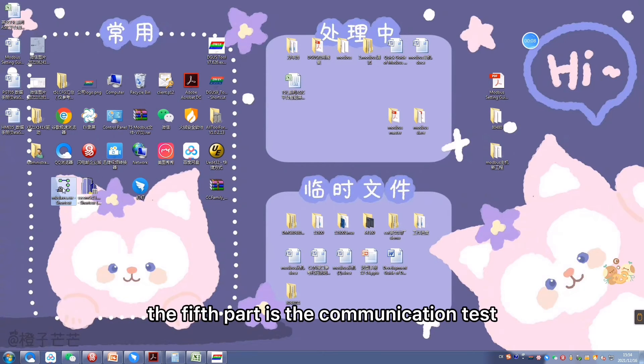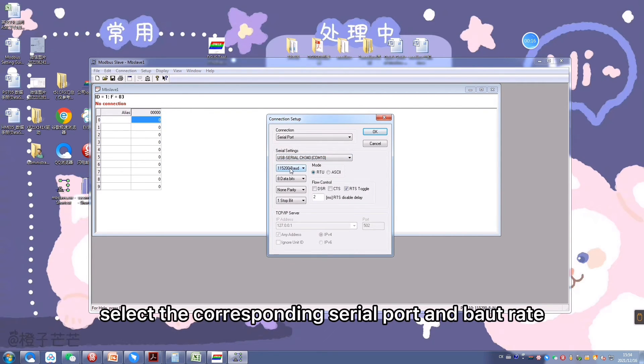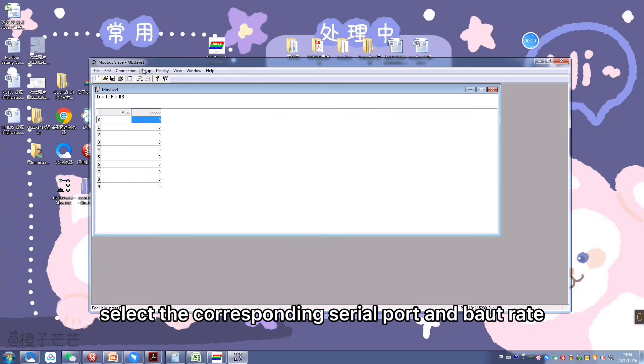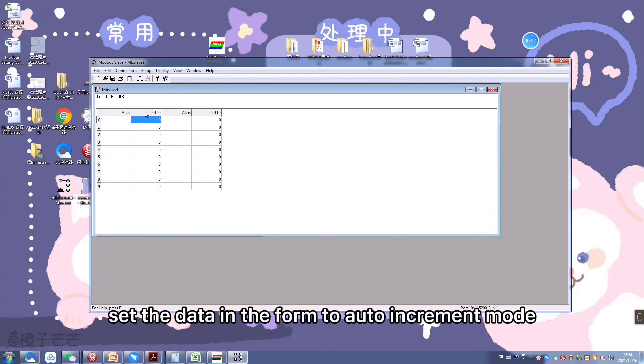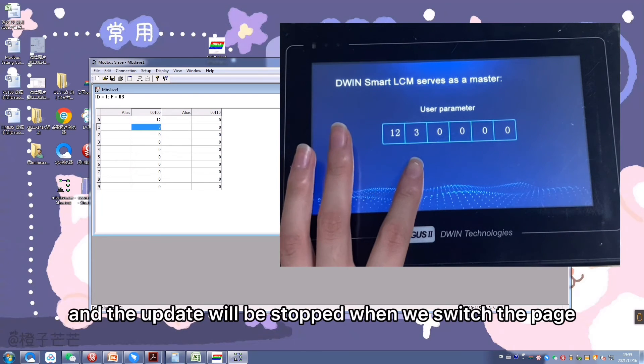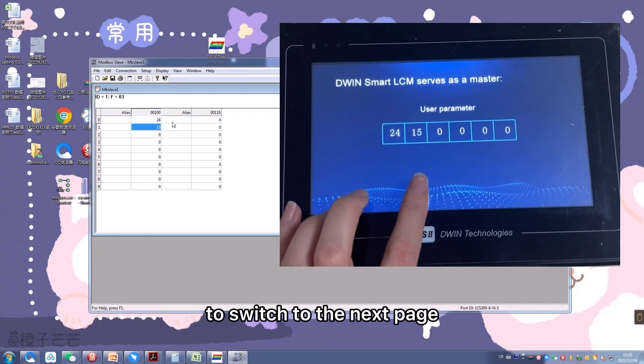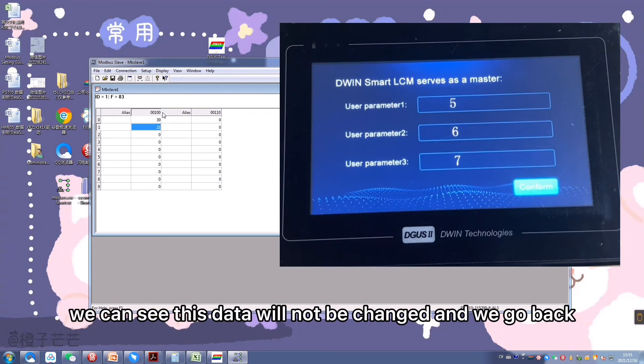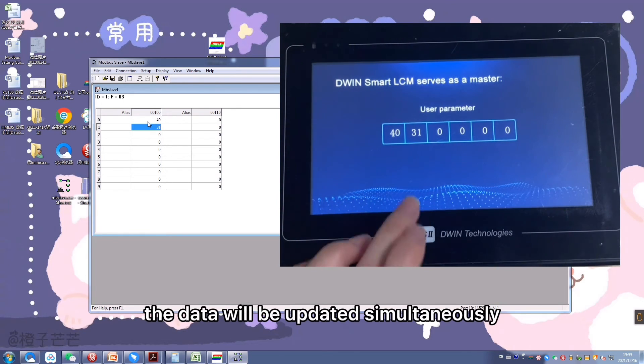The fifth part is the communication test. First, open the software Modbus Slave. Select the corresponding serial port and baud rate. Set the address to 100 and the quantity to 20. Set the data in the form to auto-increment mode, and you can see the simultaneous update on the screen. The update will be stopped when we switch the page, such as when we touch the screen to switch to the next page. We can see the data will not be changed, and when we go back, the data will be updated simultaneously.